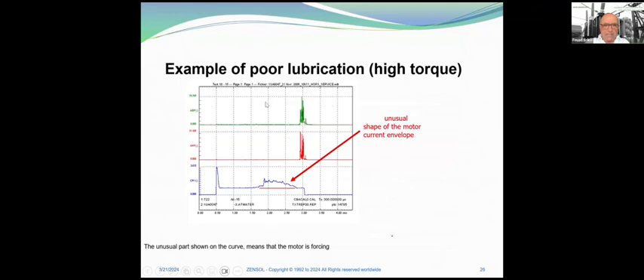Here it's an example of poor lubrication. The unusual part shown on the curve means that the motor is forcing. Usually it's totally flat. And here, immediately you can see that something is not normal in the motor drive.